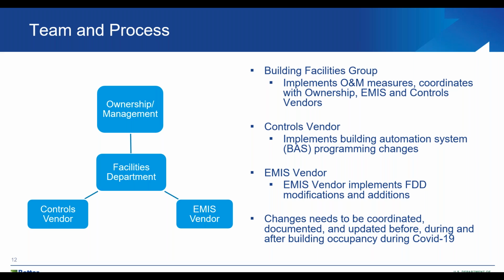And you wouldn't be operating it under any conditions very effectively that way also, if one's not talking to the other. So we don't want things operating in isolation. So in the facilities group, for example, they may still change the filters on the old schedule, but now that you have MERV 13 filters added, well, the frequency probably needs to be more frequent than that.